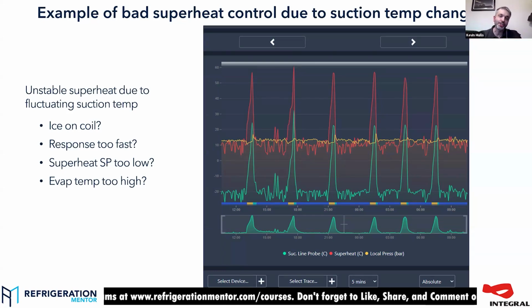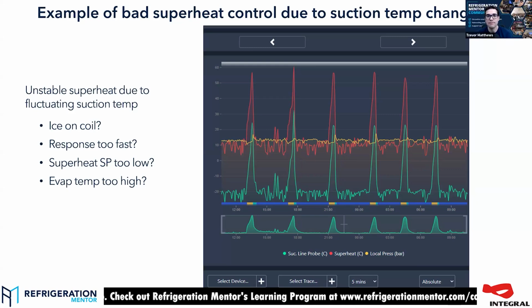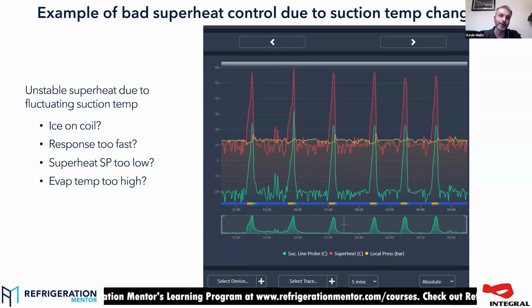Evap temp too high is just related to things like floating suction. So if you've got two different racks servicing a meat room and you're set for 0 degrees C, let's say you've got an evap temp of 5 and a superheat set point of 6. You can't achieve that 6K superheat if your return air is 0 and your evap temp is 5, because your suction can never be warmer than the air coming into the coil. Can't do it. That's what's determining that temperature, and that will make you unstable because you're trying to hit a superheat set point that's impossible. So it's one of the things to watch with floating suction. It can very easily upset your system.